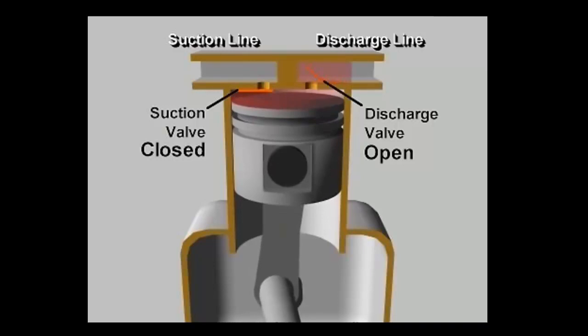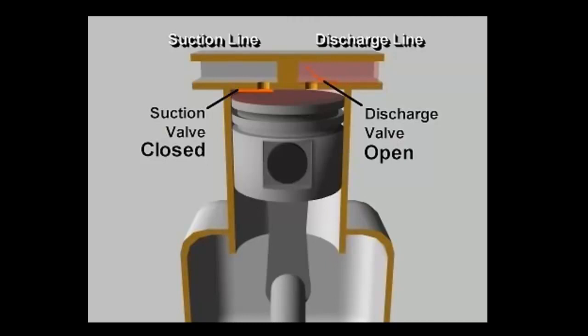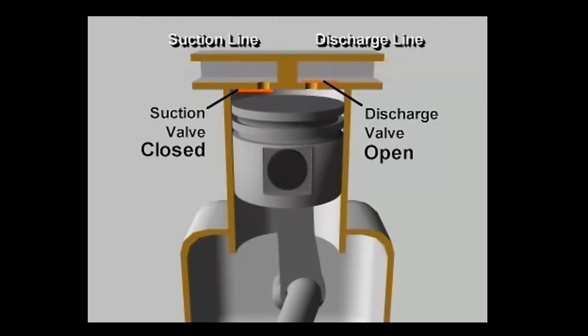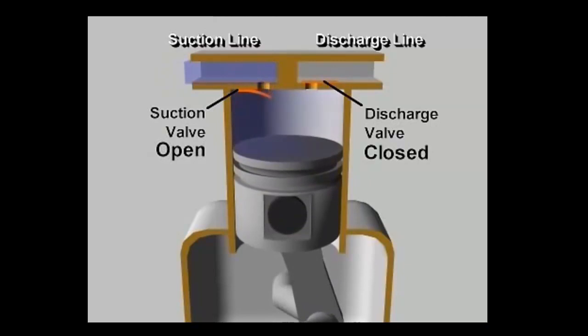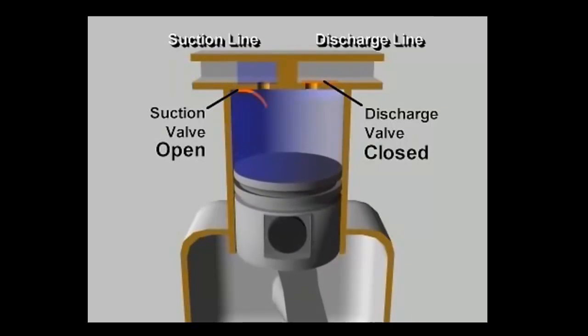This continues until the piston reaches the top of its stroke and most of the compressed vapor has been expelled into the discharge line. When the piston begins its downward stroke, the discharge valve closes. The complete cycle then repeats during each revolution of the crankshaft.